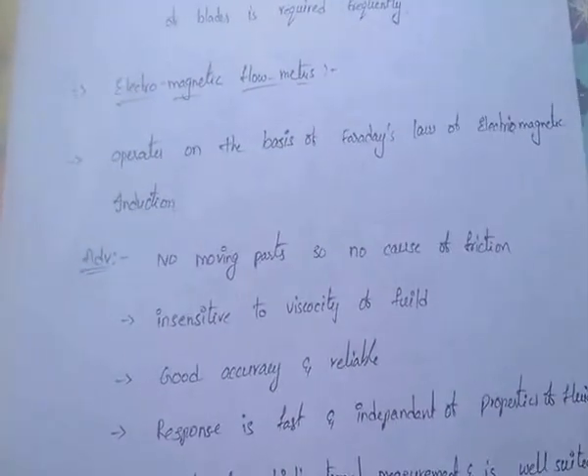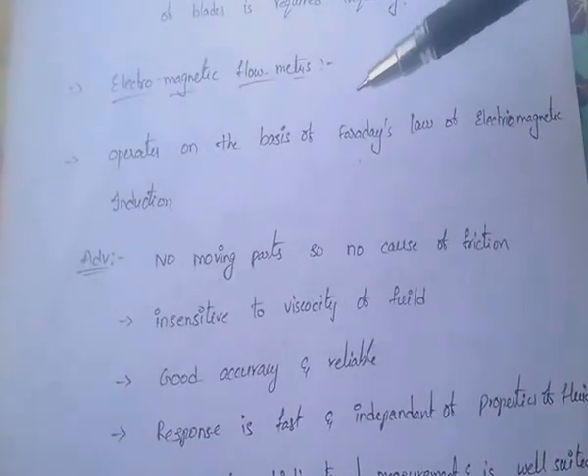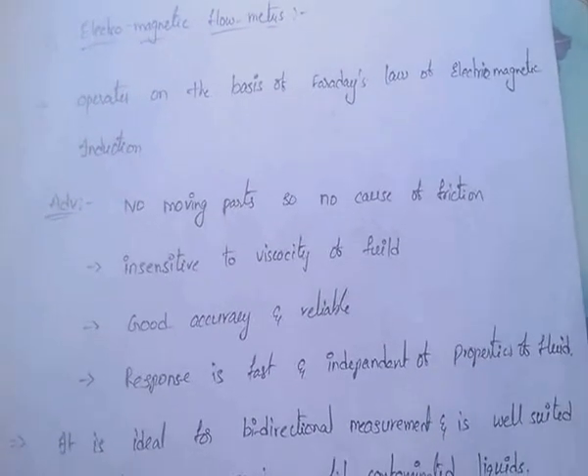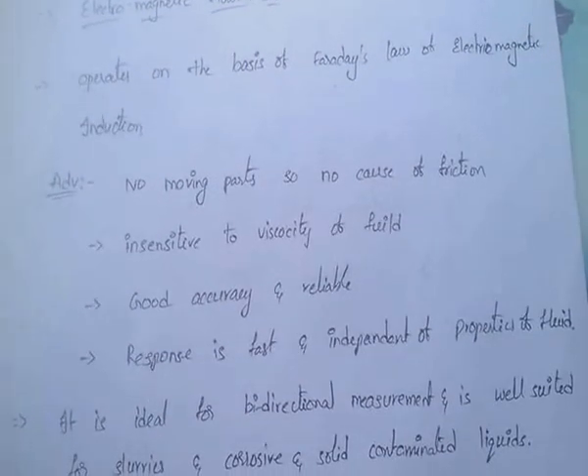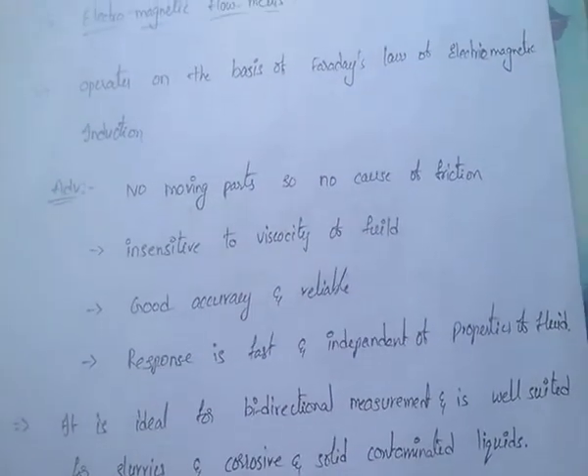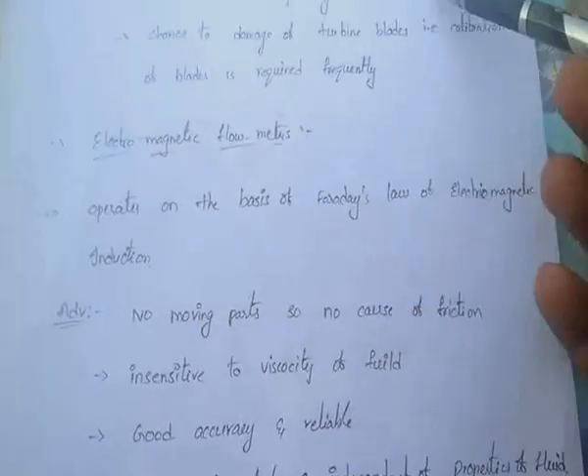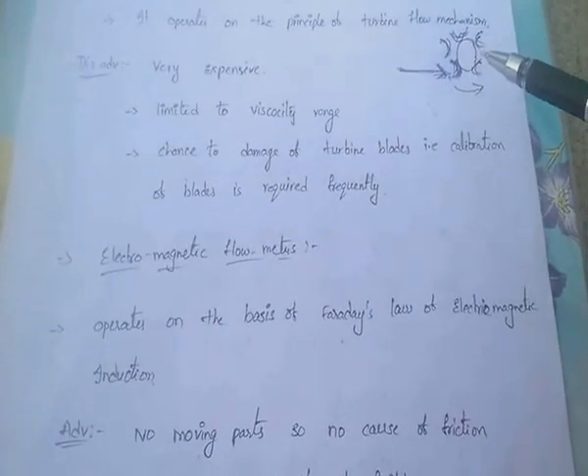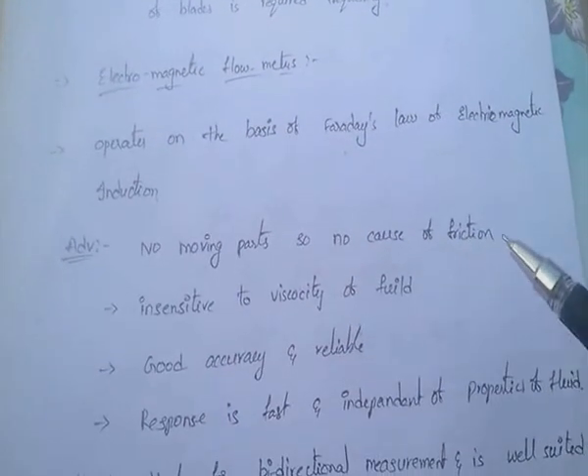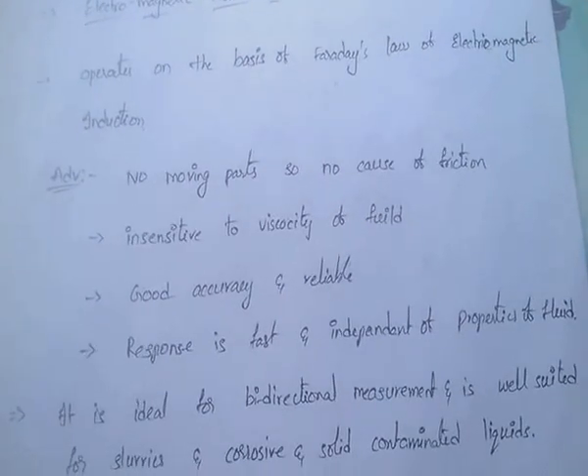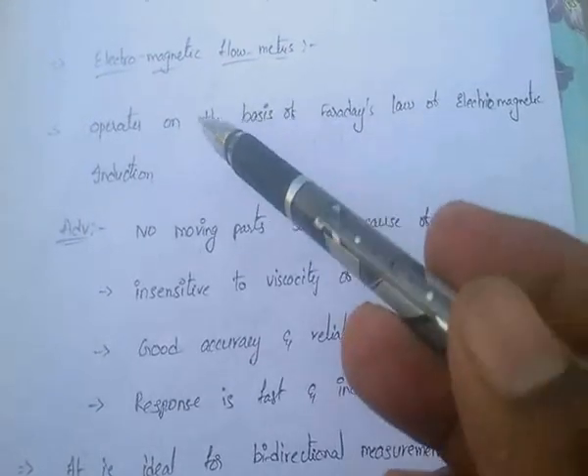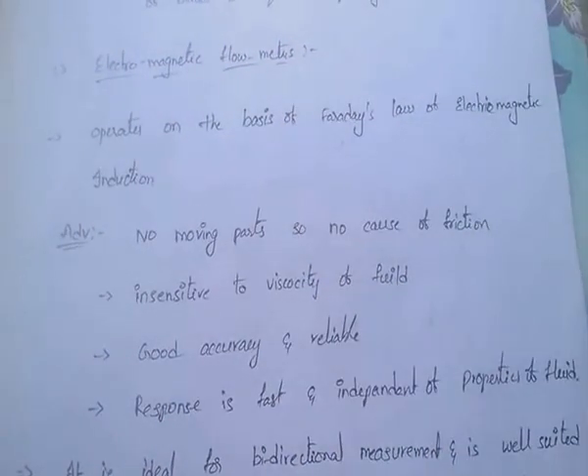To overcome these disadvantages, electromagnetic flow meters were developed. Electromagnetic flow meters operate based on Faraday's laws of electromagnetic induction. The advantages of electromagnetic flow meters include: no moving parts, so there are no friction losses. They are also insensitive to the viscosity and properties of the fluid, meaning they are independent of fluid properties.